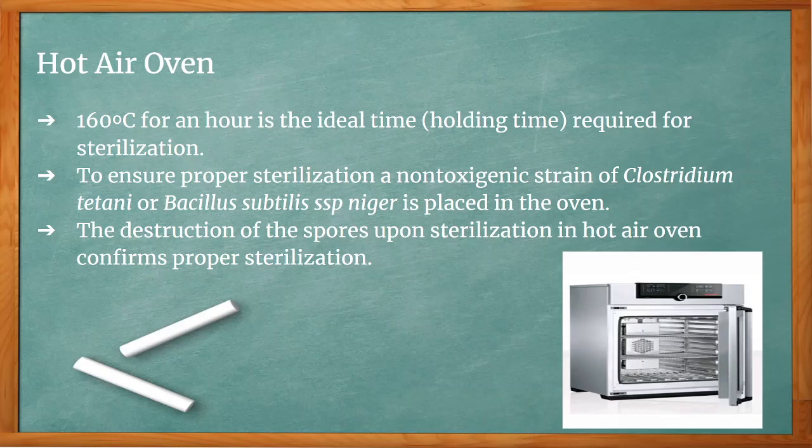To ensure proper sterilization, a non-toxigenic strain of Clostridium tetani or Bacillus subtilis subspecies Niger is placed in the oven. The destruction of the spores upon sterilization in the hot air oven confirms proper sterilization.